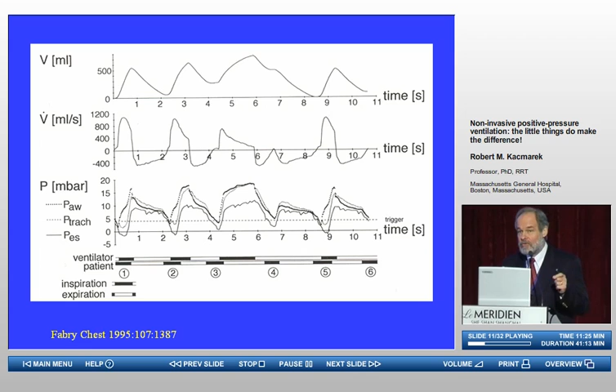overall ventilatory demand. This was from a publication now over 10 years ago that looked at the impact of CO2 rebreathing with these bi-level pressure ventilators. Remember, every one of them that I'm aware of on the market has a single limb gas delivery system. Exhalation occurs through some small orifice somewhere in the mask or in the tubing itself. These ventilators have very low internal resistance. So if you have very low level or zero PEEP set on these units, it is possible exhalation can move retrograde all the way through the tubing back to the mechanical ventilator, and of course allowing CO2 to be inspired on the next breath, which is exactly what this group showed with a series of ventilators.